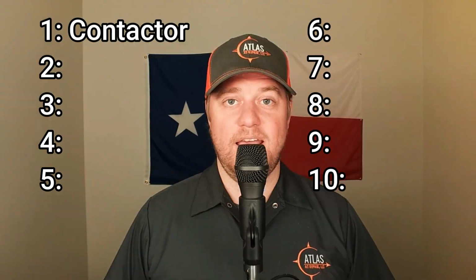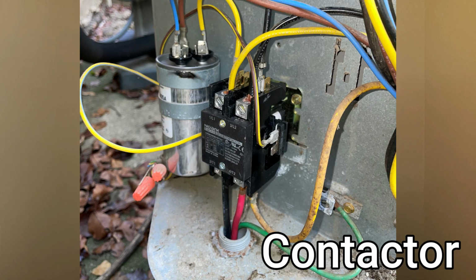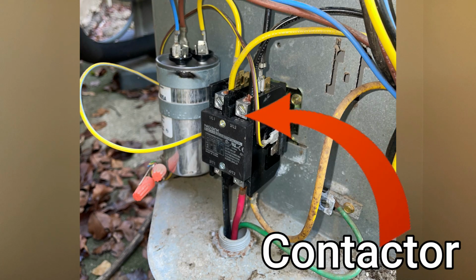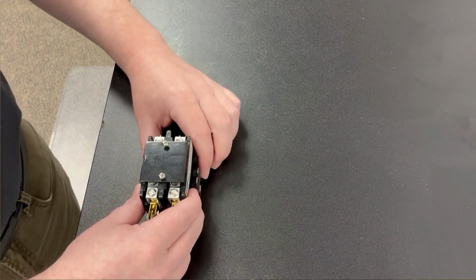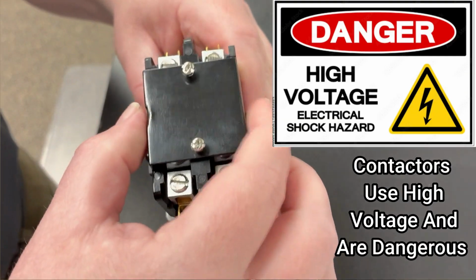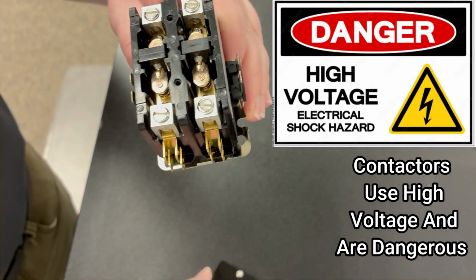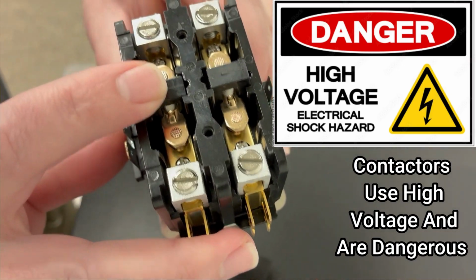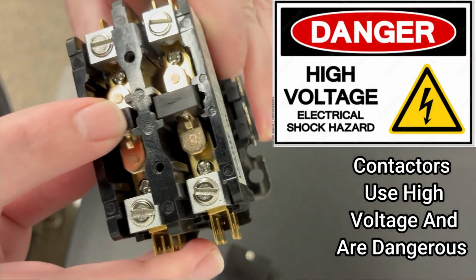So our first wear and tear component is the contactor, and it is responsible for turning on and off the outdoor unit. So basically how a contactor works is it has a plunger that springs in and out of place to make the power connection or disconnect the power. So when the thermostat calls, it closes, and when the thermostat is satisfied, it opens. And after doing this a million times, it just starts to wear out.